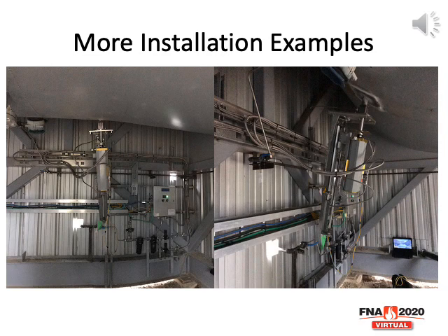Especially for the air that's purging the lens, it's critical that this be clean air because it's going through the optics and we don't want to get oil or moisture onto the optics. So in the picture on the left, you can see in the lower right the air filter and some of the regulators that are bringing in the air, regulating it to the appropriate pressures, and making sure that it's filtered before it goes through the lens system.